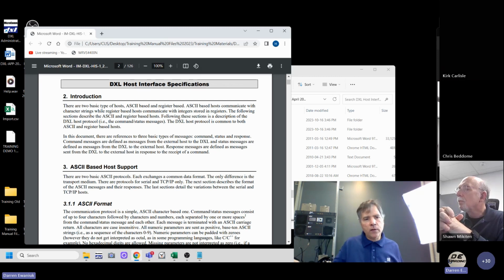It'll tell you the master number that the call is coming into. It'll tell you the station number that's calling in. So it's a command followed by 1 to 4 arguments, depending upon the command. The other is the PLC interface. The intercom system can simulate a PLC, so it can look like a PLC on your system. Anything on your system that can control a PLC can control the intercom system. It's just another PLC on the network.